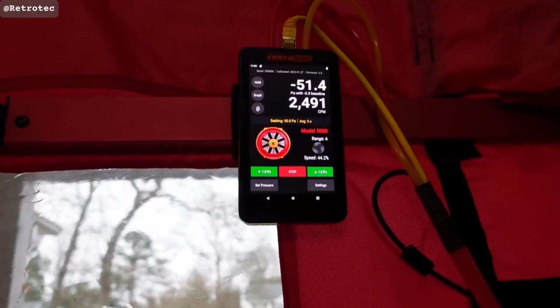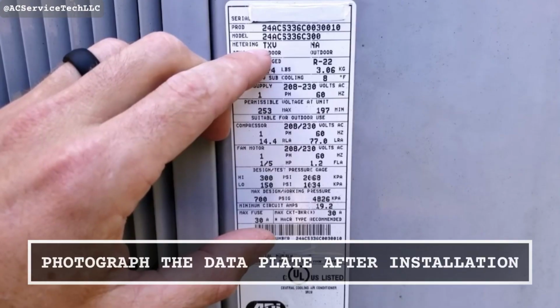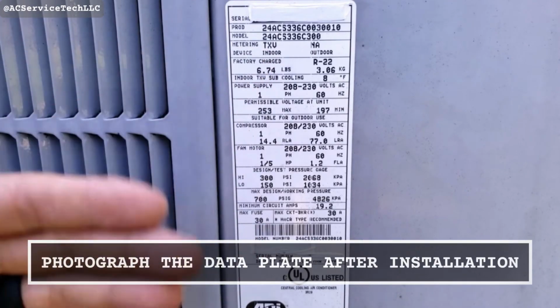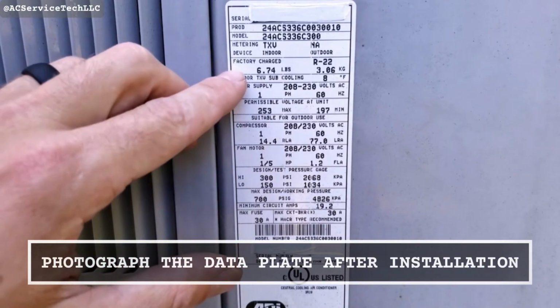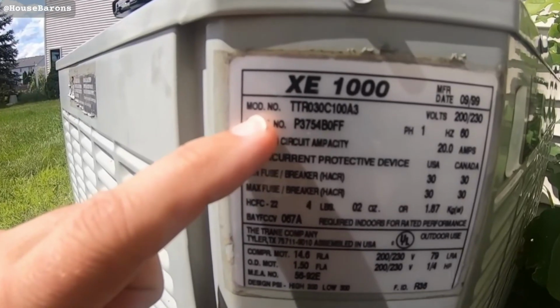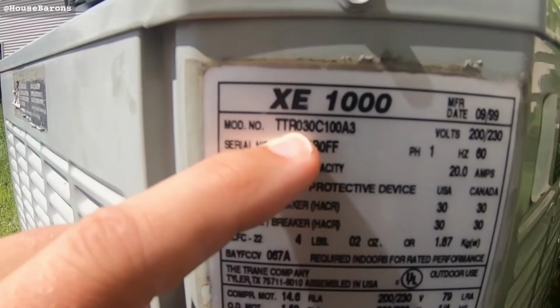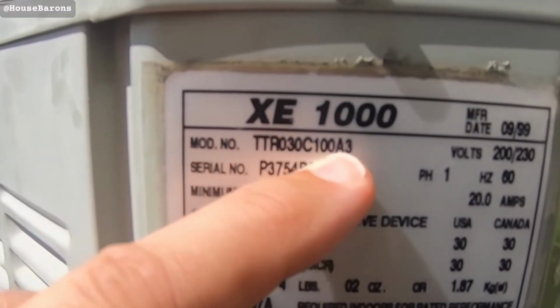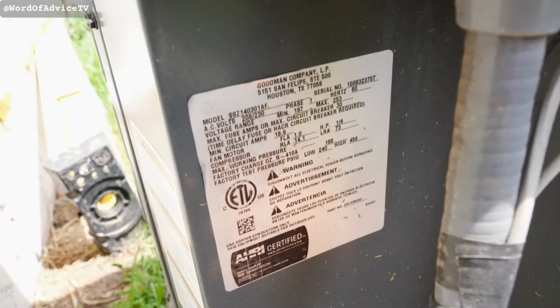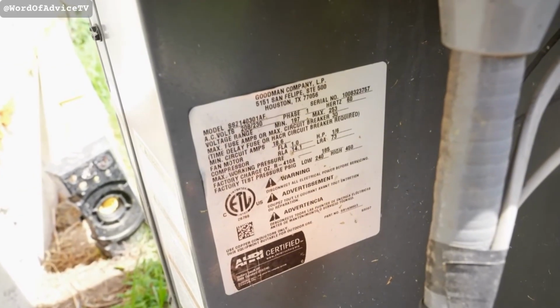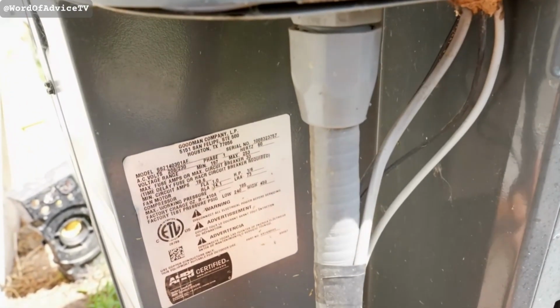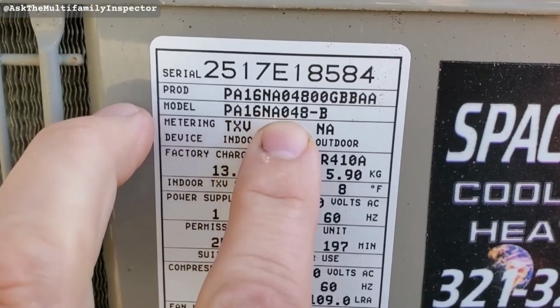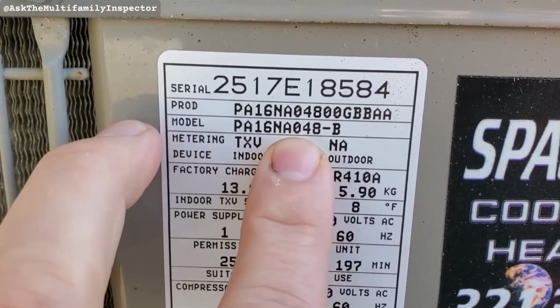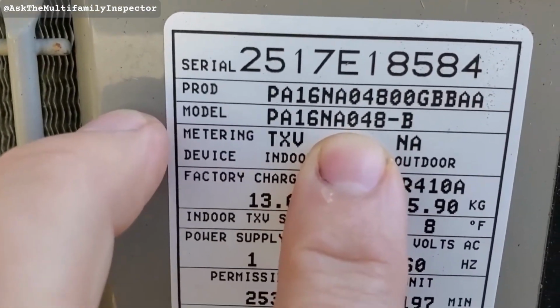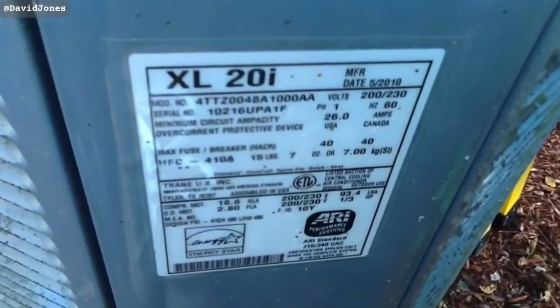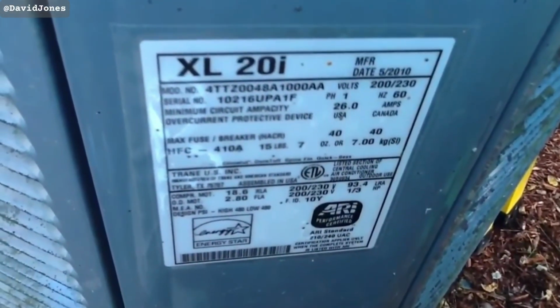Number 33. The day a contractor finishes installing new equipment, walk outside with a phone and photograph the data plate on the new condenser. Get the model number, serial number, refrigerant type, charge weight, and SEER rating in the photo. Some contractors, not many but enough to matter, will install a different SEER tier than what's on the contract and leave the old data sticker, betting you'll never check. The photo protects you on warranty claims and on resale disclosures.